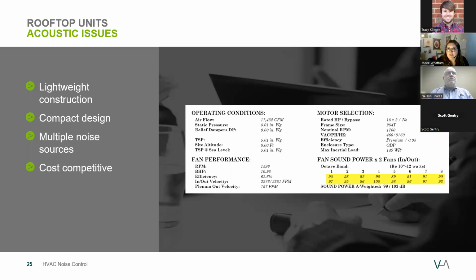RTUs are built lightweight and are made to be as small as possible. They achieve compact designs by including smaller fans, and to achieve higher flow rates, these fans need to operate at very high RPMs. A compressor is also one of the multiple sources of noises from an RTU as well. And unfortunately, there's little to no money left in competitive pricing for noise control. Shown on this slide is the fan sound power levels of an RTU shop drawing. We've got near triple digit values in some of the octave bands.